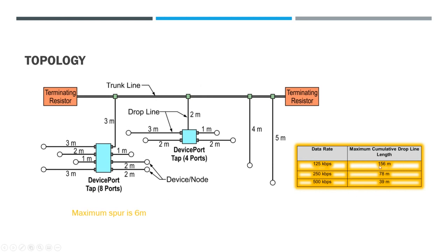For example, if I had a cumulative drop line length of 156 meters, I could only transmit data at this speed. If my drop length totaled a lower value, you could have more data speed. Lower value or fewer meters means faster data rate. But at a bare minimum, the maximum spur or drop length is 6 meters. You'll see here none of these drops are longer than 6 meters.